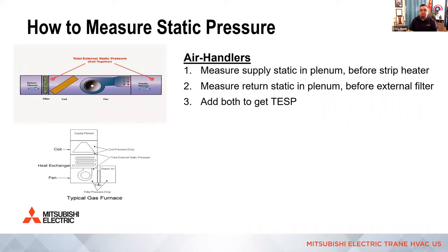What ends up being tougher is when you have, let's say, a furnace, a high efficient filter cabinet, and you throw an A coil on top of a furnace. And now we have to try to measure as close to that furnace as possible. So typically, myself, what I would do is measure in the blower compartment and measure where the high limit switch used to be. I'd have to pull it out, put the probe in where the high limit switch is, because it's previous to the A coil, because those filter boxes and A coils are not shipped with the furnace as part of that package, right? So you have to account for that pressure drop. If you measure after it, you're going to measure a much lower pressure in the supply compared to what it is prior to the coil. And that's not really how the system's running, all right?